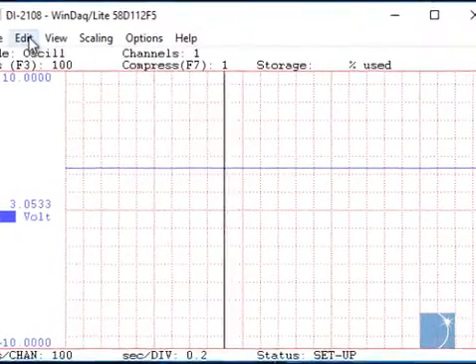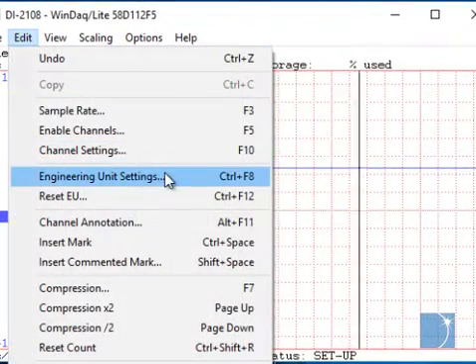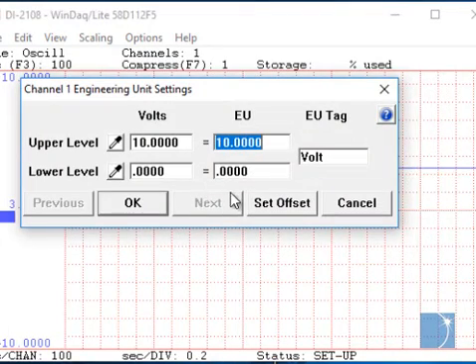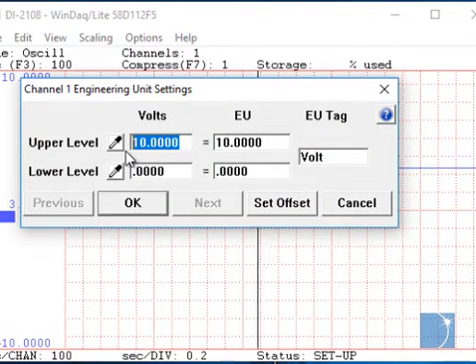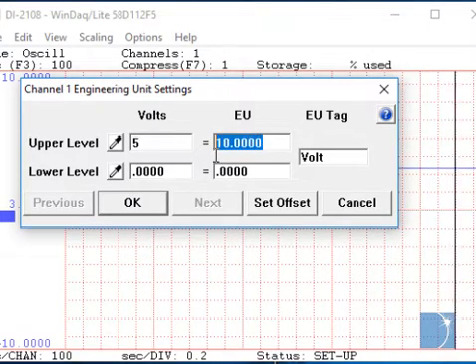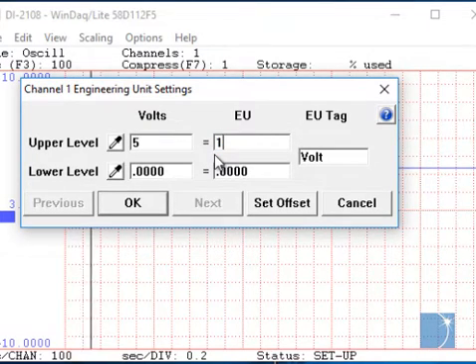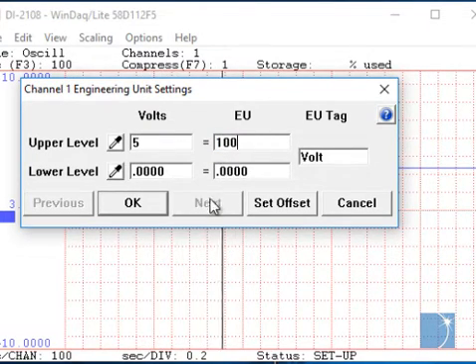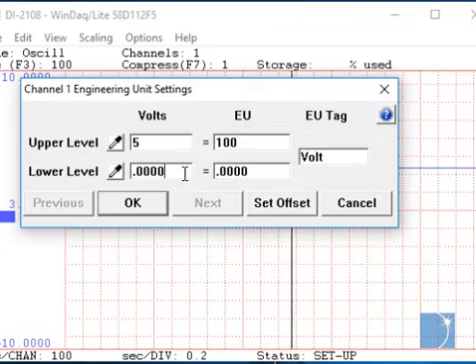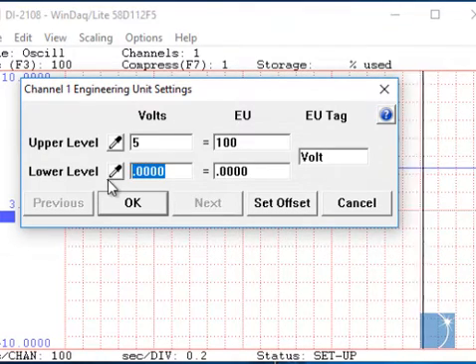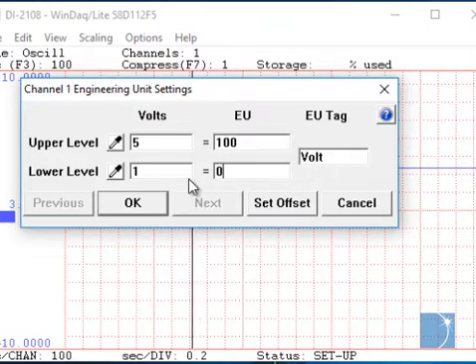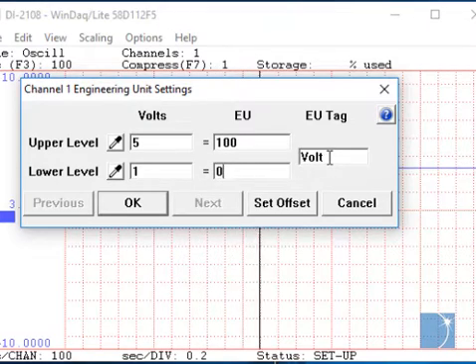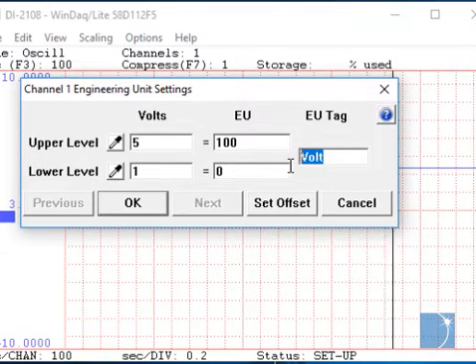Using the engineering unit settings feature in WinDaq, we can scale the 1 to 5 volts into meaningful engineering units — in this case pressure. We'll set 5 volts equal to 100, 1 volt equal to 0, and change the EU tag to PSI.